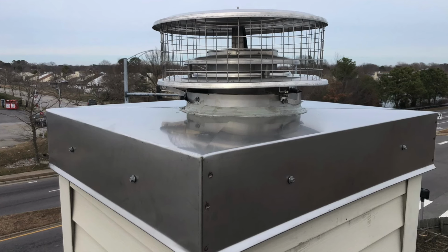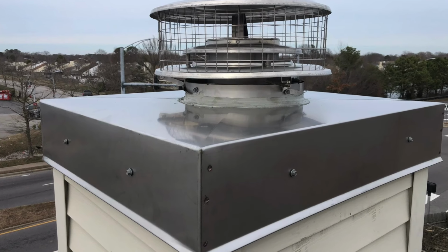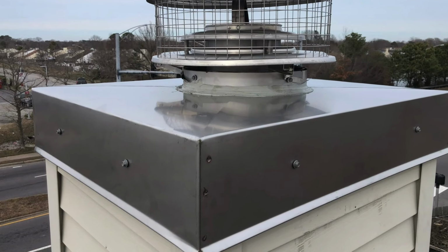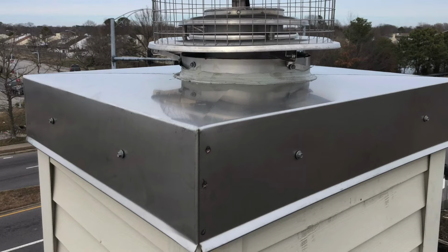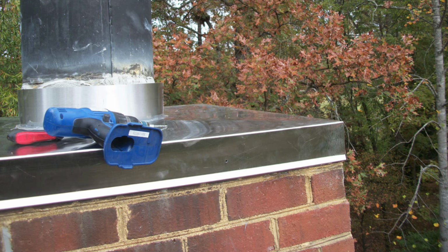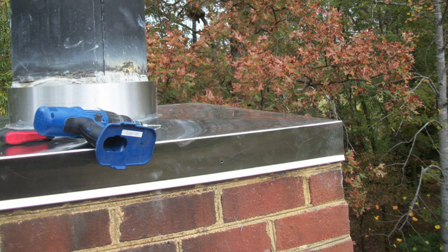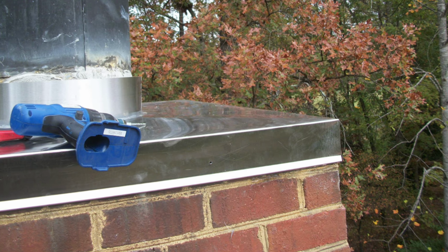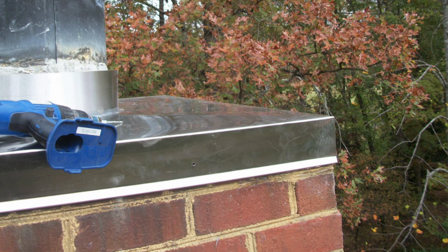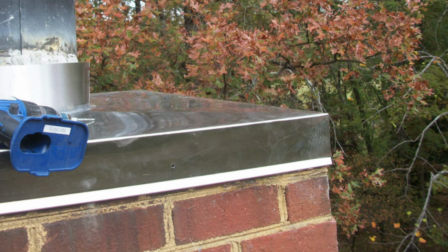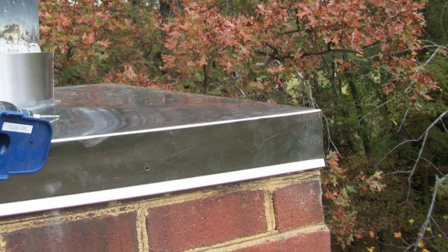For non-masonry systems, metal chimney crowns are required to lap a minimum of 4 inches down the sides of the chimney and must include a flared drip edge. This extended lap protects the vertical surfaces from water intrusion at the crown to masonry interface, while the drip edge ensures water detaches cleanly rather than running down the structure.